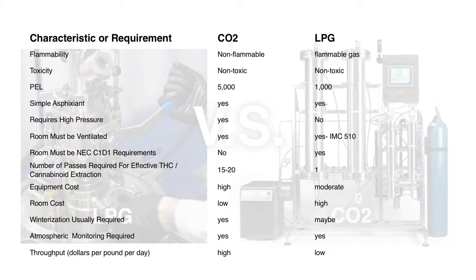The CO2 room has to be ventilated, but the ventilation requirements are fairly minimal. We need a number of air changes per hour to make sure that if there is a release of CO2, it is ventilated and removed. But for LPG, we have to have much, much higher ventilation rates. If we need to meet the International Mechanical Code 510 requirements, as we do in Denver, then the rates are almost 100 air changes per hour. So we're looking at very high air exchange rates to make a safe environment.